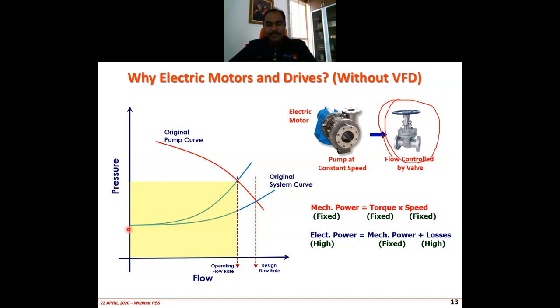Normally, when we design, we will have a system curve, the original system curve. We will be designing it for one particular design flow rate. So let's say we are designing at this particular point. Then once we have decided, we install the pump and start to operate it. But when you operate the pump, usually we don't run at this particular flow. Usually we'll be running at a reduced flow rate, and let's say over here is the operating flow rate.